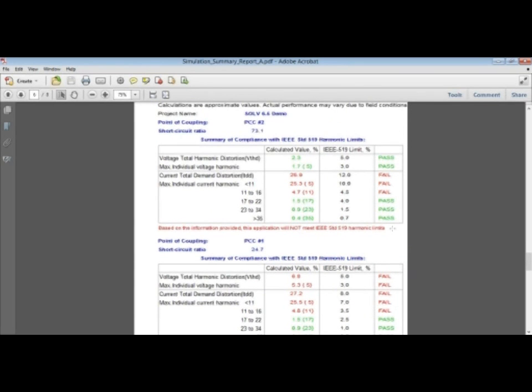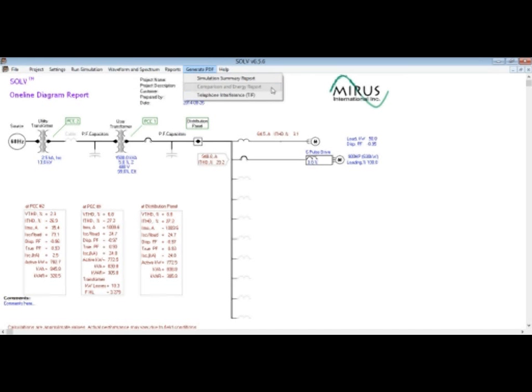On the compliance report, you can see that we don't meet IEEE 519 compliance for the system, that basically we fail meeting harmonic limits on both points. Closing this report, we also have a comparison energy report here that provides the summary of the differences between the 2 scenarios, but I will demonstrate this later.